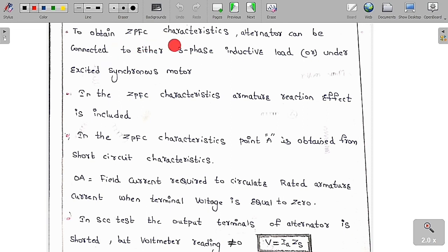To obtain the ZPFC characteristics, the alternator can be connected to either a three-phase inductive load or an under-excited synchronous motor, because an under-excited synchronous motor acts like an inductive load, whereas an over-excited synchronous motor acts like a capacitive load. So under-excited synchronous motor acts like a three-phase inductive load, whereas over-excited synchronous motor acts like a three-phase capacitive load.